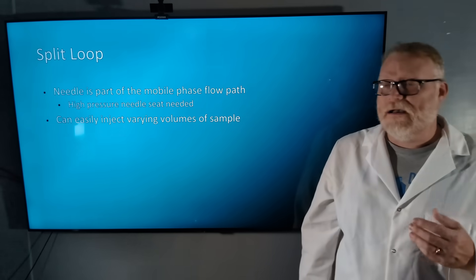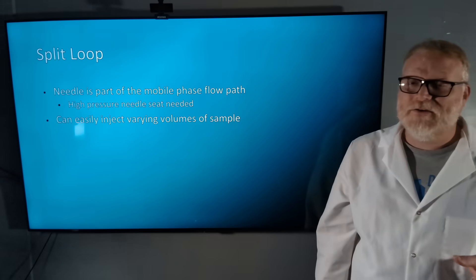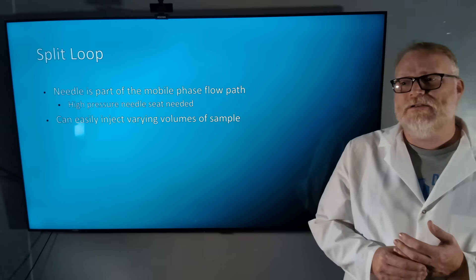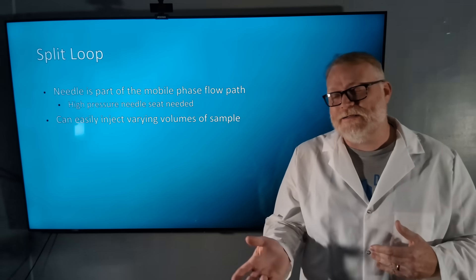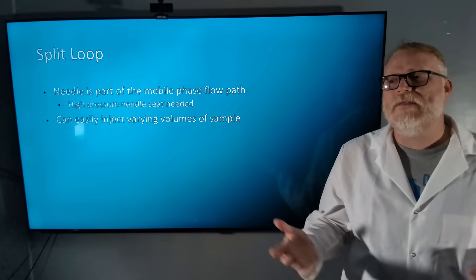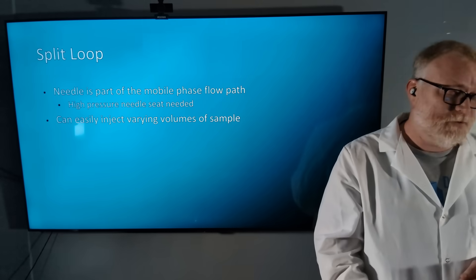It can do varying volumes of sample. So this way you can do, if you wanted one injection to be 10 microliters and the next one to be 7 microliters, you can do that without changing the sample loop.